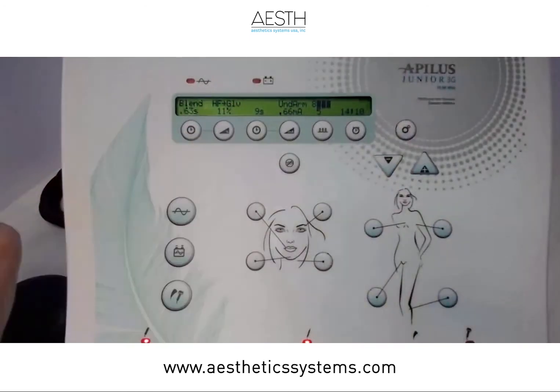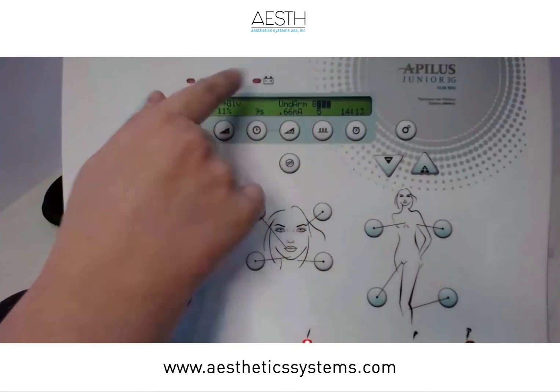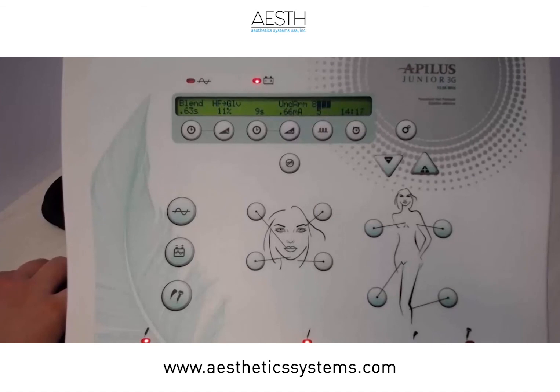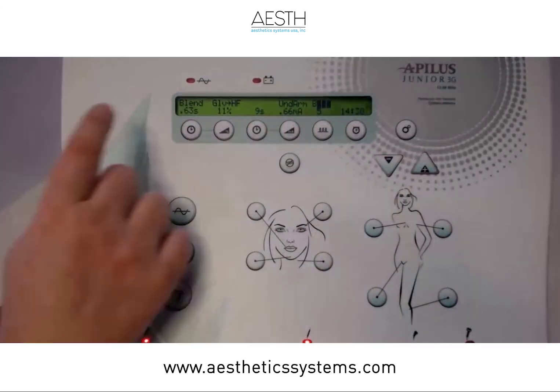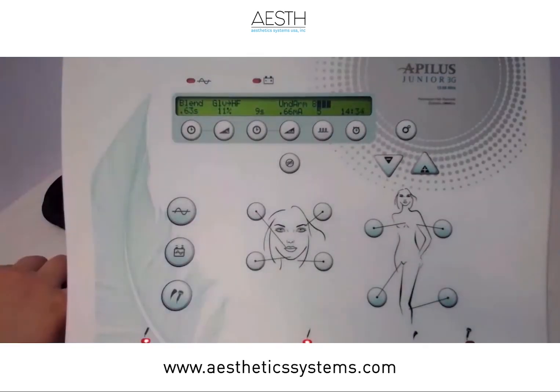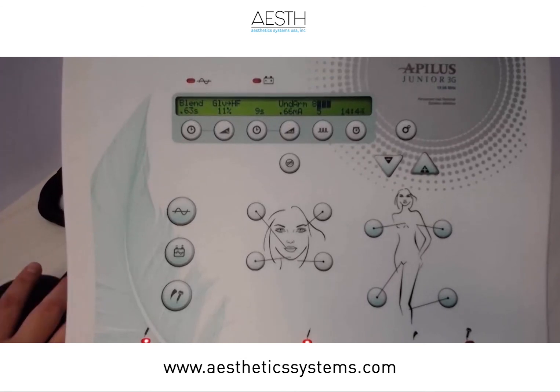It took me back to my screen, and now what I see is high frequency first, galvanic second. So now if I press on the foot pedal, I will have a pulse first, then my galvanic will turn on. There you go. Let's go back and put our lead back into galvanic. It flips it. Now galvanic is first, high frequency is second. When I press on my foot pedal, my galvanic lights first, then we have our pulses. I won't do this the whole time. One thing to keep in mind: as soon as you take your foot off the pedal, it interrupts the setting and no more current goes through. So you want to make sure that you hold the foot pedal down for as long as necessary to go through the whole pulse.